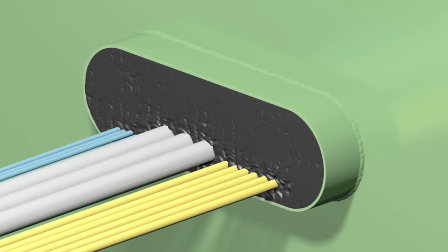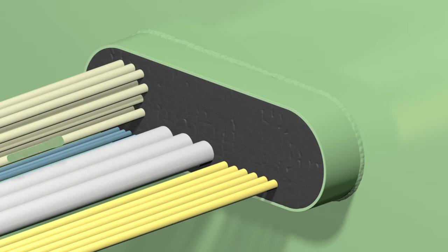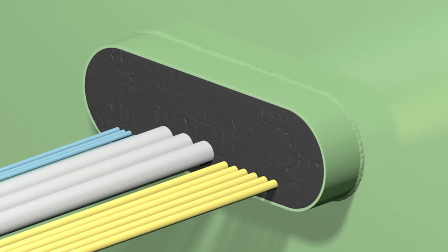The FIWA sealant between the cables is pressed down firmly. A special tool developed by Beele Engineering with a PTFE compression smoothing part is available. The sealant will not stick to the PTFE. Compression and smoothing, especially in between the cables, is essential to obtain an effective gas and water tightness. Especially when lots of cables are installed, a last check should be made to ensure that the sealant layer is pressed down tightly. Air enclosure in the sealant layer should be prevented during finishing because this would have a negative impact on the performance of the sealant layer under fire exposure.